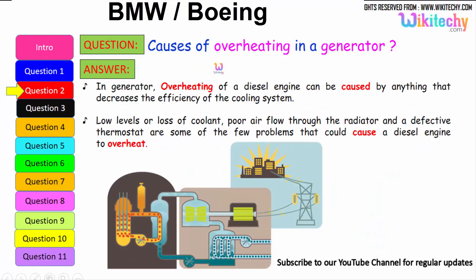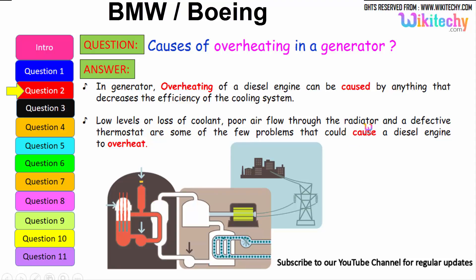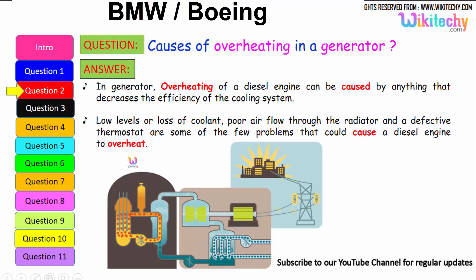The next question: causes of overheating in a generator. Overheating of a diesel engine can be caused by anything that decreases the efficiency of the cooling system. It can be due to the loss of coolant or low levels of coolant, poor airflow through the radiators, and a defective thermostat — these are some of the problems that could cause a diesel engine or generator to overheat.